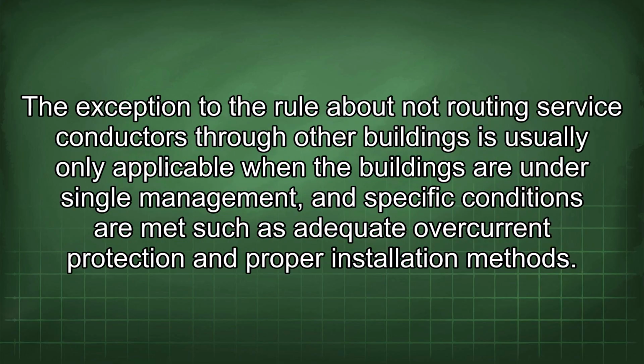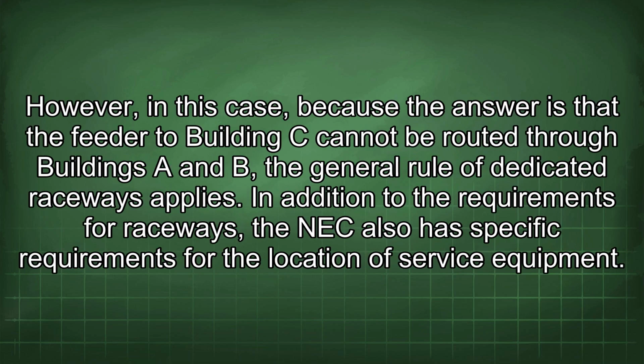The exception to the rule about not routing service conductors through other buildings is usually only applicable when the buildings are under single management, and specific conditions are met, such as adequate overcurrent protection and proper installation methods. However, in this case, because the feeder to Building C cannot be routed through Buildings A and B, the general rule of dedicated raceways applies.